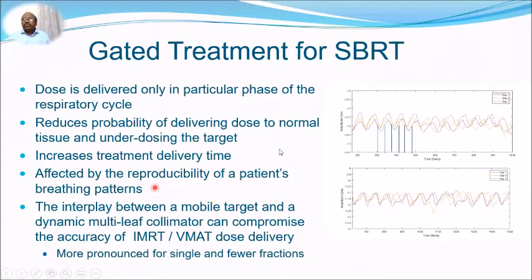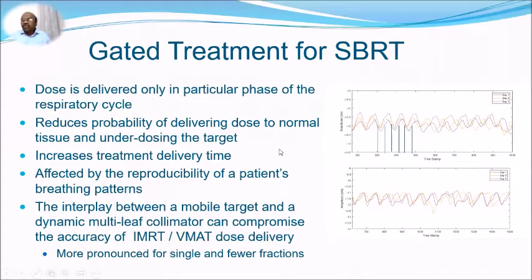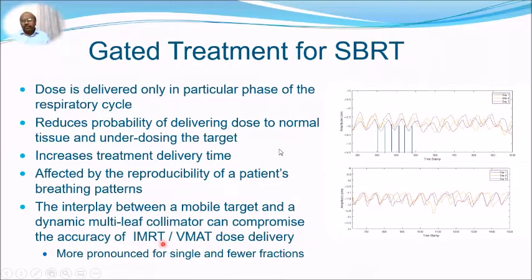Gated treatment is affected by the reproducibility of the patient's breathing pattern, which can significantly vary from day to day. There is also an interplay between the mobile target and the dynamic multi-leaf collimator that can compromise the accuracy of IMRT or VMAT dose delivery. This interplay effect is very pronounced for single-fraction or few-fraction treatments; with many fractions it tends to average out. For 3D-CRT it is not an issue, but for IMRT or VMAT this interplay must be considered.